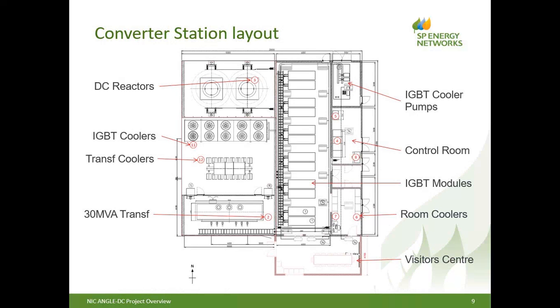To go into a bit more detail about what a converter station actually looks like inside, what will be inside that big red box on the previous slide, it's made up primarily of the transformer, which is the bottom left, item 2. Transformer coolers is item 12. We've also got the IGBT, which are the thyristor bank coolers, which is item 11. And we've also got some DC reactors, which is item 3.